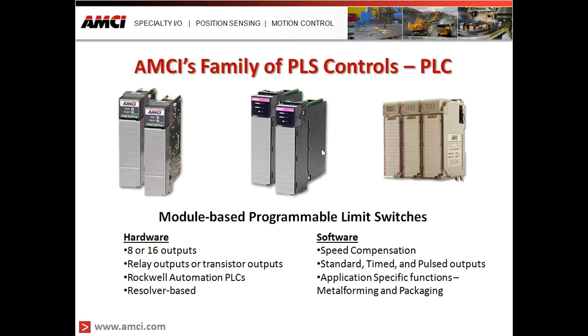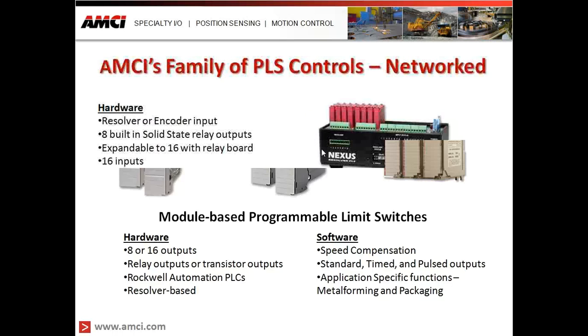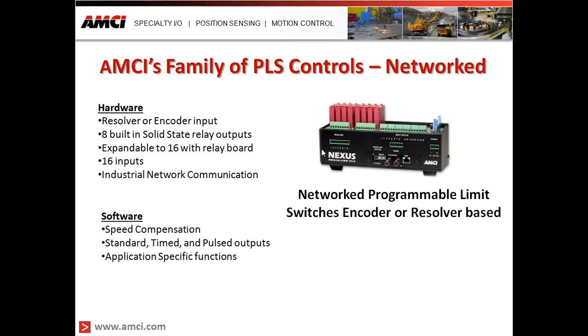For network solutions, AMCI offers the Nexus PLS. It is either resolver or incremental encoder based, with 8 built-in solid-state relay outputs expandable up to 16 with a relay board. It can be programmed from any PLC using industrial networks such as EtherNet/IP, PROFIBUS, or Modbus TCP. Standard software features include speed compensation, timed outputs, and application-specific functions. This is ideal for systems where no plug-in module exists, or where rack space is limited and you want to remotely mount the PLS closer to the sensor or machine, using the network connection for programming.